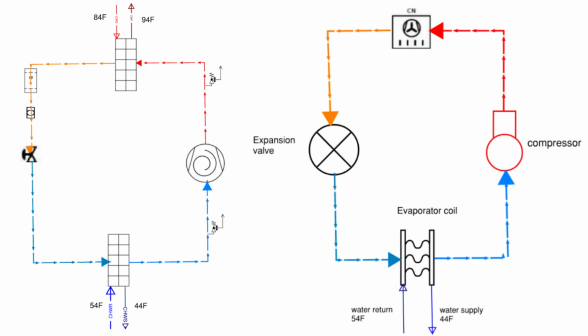Every heat pump or chiller has two main sides of the refrigeration circuit. The high pressure side, which includes the compressor discharge and condenser, and the low pressure side, which includes the evaporator and the suction line. When pressure gets too high or too low, safety sensors or pressure switches will shut down the compressor to protect the system.